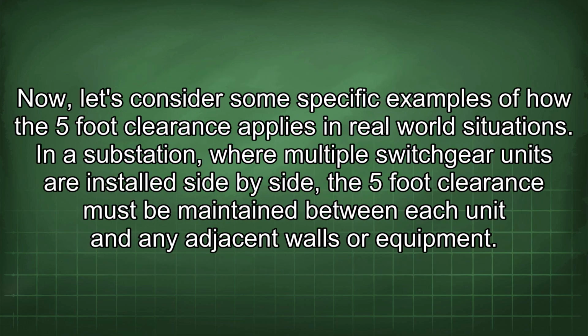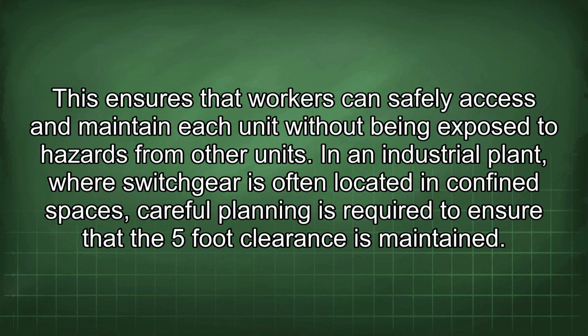Now, let's consider some specific examples of how the 5-foot clearance applies in real-world situations. In a substation, where multiple switchgear units are installed side by side, the 5-foot clearance must be maintained between each unit and any adjacent walls or equipment. This ensures that workers can safely access and maintain each unit without being exposed to hazards from other units.